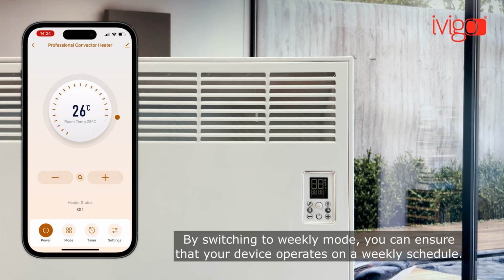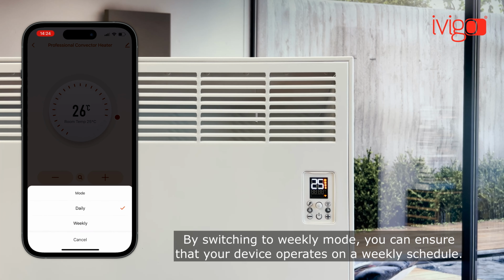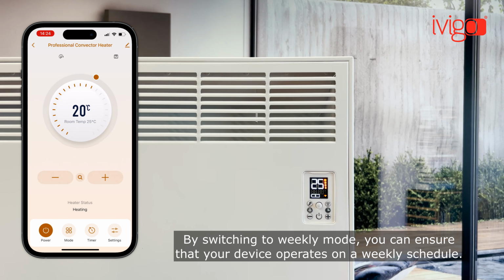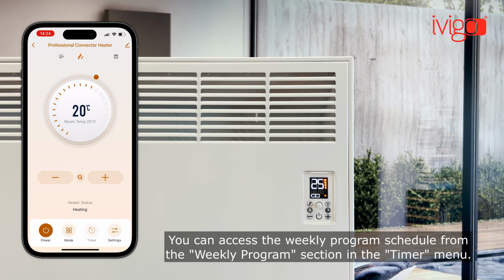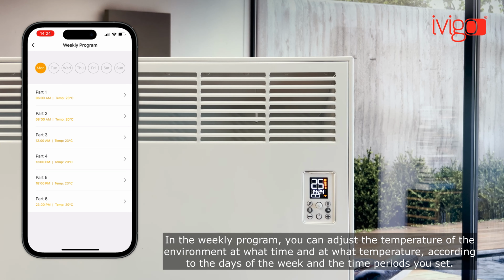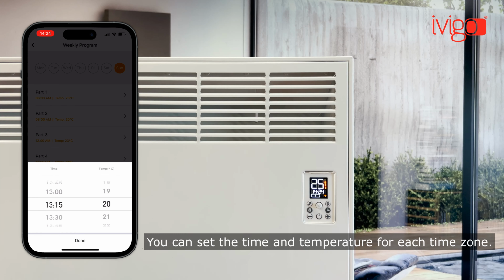By switching to weekly mode, you can ensure that your device operates on a weekly schedule. You can access the weekly program schedule from the Weekly Program section in the Timer menu. In the weekly program, you can adjust the temperature of the environment at what time and at what temperature, according to the days of the week and the time periods you set. You can set the time and temperature for each time zone.